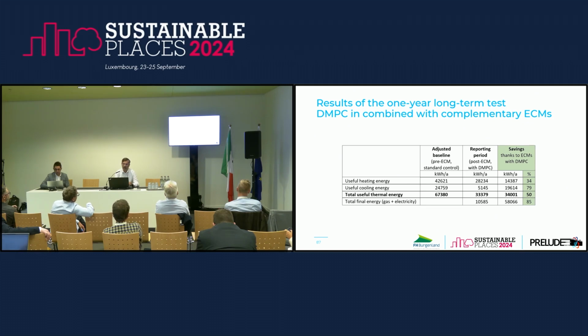And if you remember, I told you that we made the decision that for the long-term test we also switched off the gas boiler and used only the heat pump for space heating and space cooling. Therefore the 58,000 kilowatt hours is largely the reduction of gas, so we don't have any gas consumption during the long-term test period.